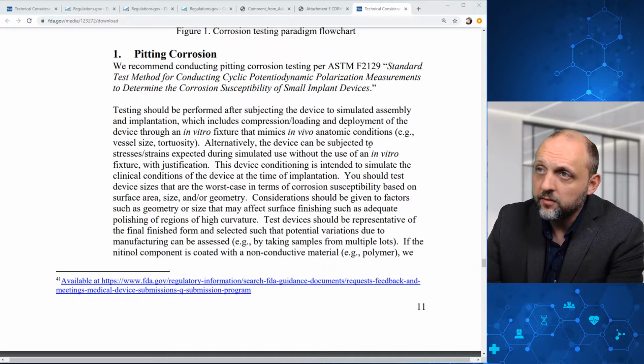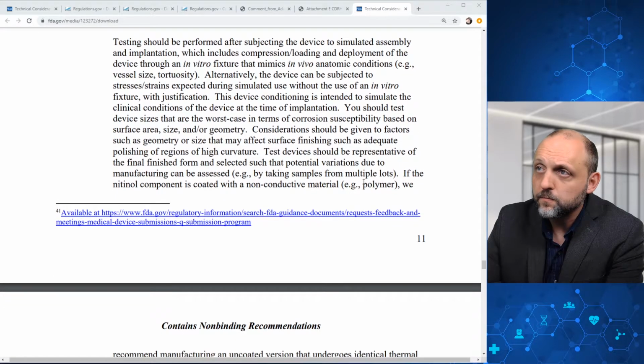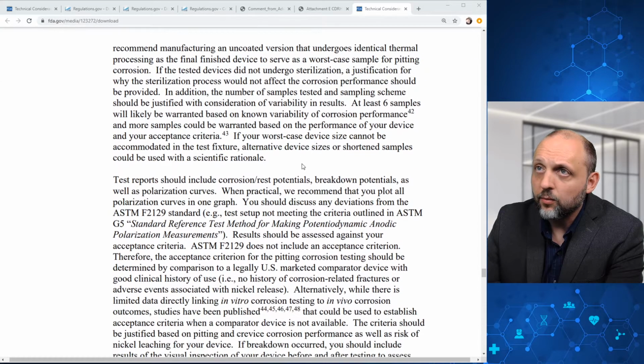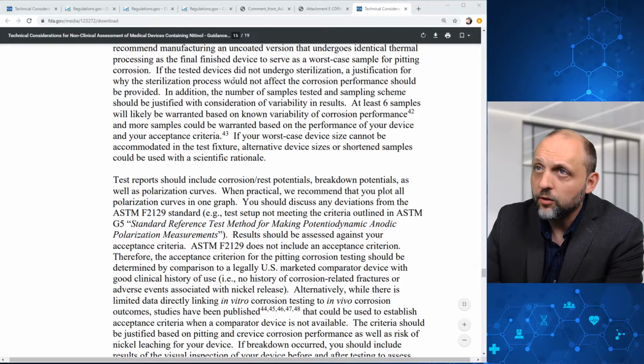And alternatively, the device can be subjected to simulated use without the use of an in vitro fixture with justification. And here, the device conditioning is intended to simulate the clinical conditions of the device at the time of implantation. And you should look at worst case scenarios in terms of corrosion susceptibility based on surface area, size, and geometry. And consideration should be given to factors such as geometry or size that may affect surface finishing. And test devices should be representative of the final finished form. And FDA recommends manufacturing an uncoated version for coated devices that undergo identical processing.